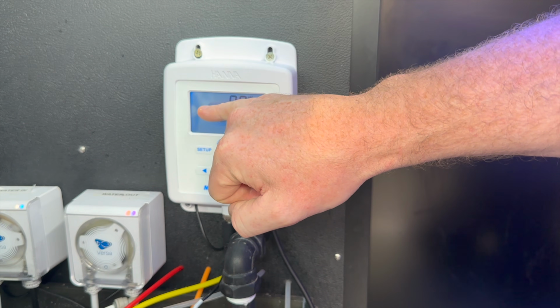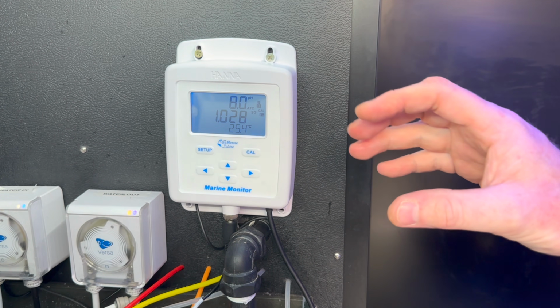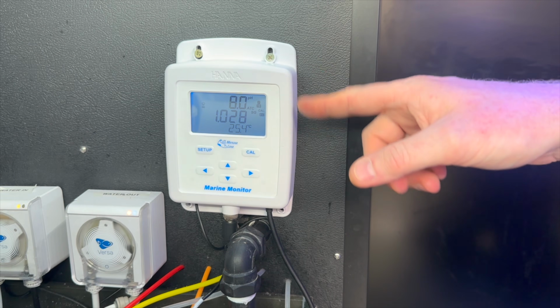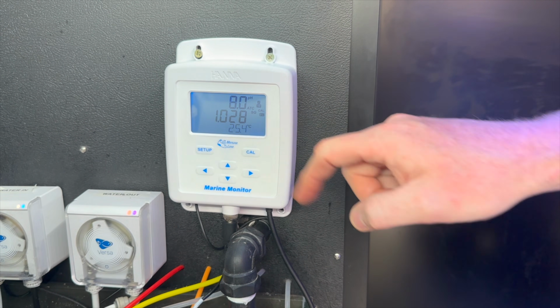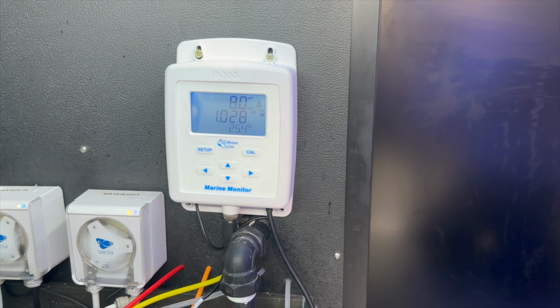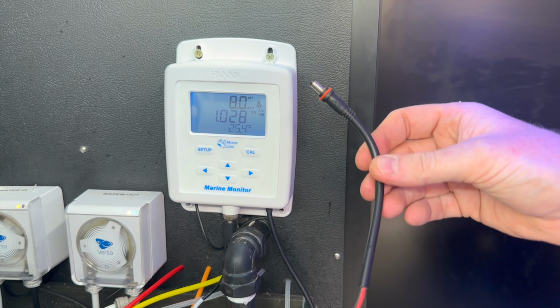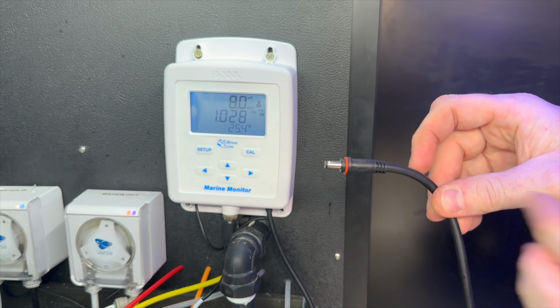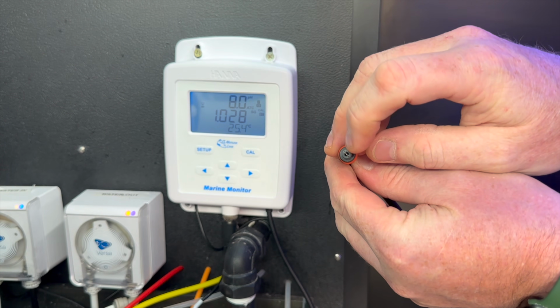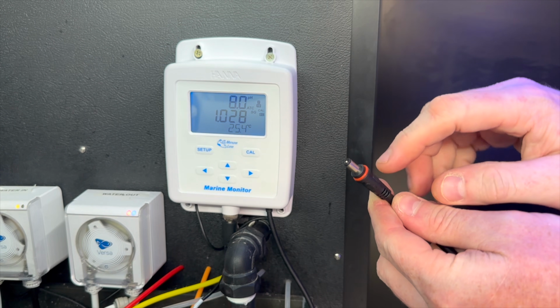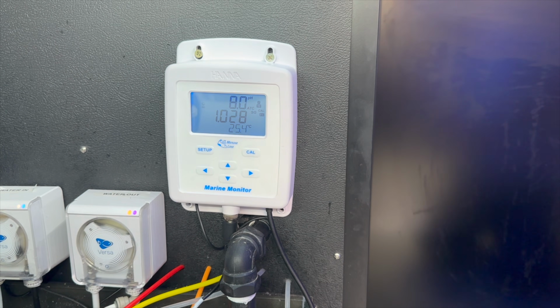Now you can see that the hourglass here on this power supply continually flashes. It's almost as if the unit is never quite happy that the results are stable enough, so it keeps checking. Also of interest, it's measuring 1.028, 1.027 specific gravity, when this tank is currently running 1.029 specific gravity. Now, if I swap that over to my own high quality power supply, and just before I do that, I will point out that for some unknown reason, Hanna has seemed to use a reverse polarity connector on their power supply. Typically, the outside sheath here is the negative and inside is positive. For some reason, Hanna have done it opposite. So the outside is positive and the inside is negative, which means the majority of power supplies out there will not work out of the box. You will need to customize them or buy a specific power supply with the polarity that way.